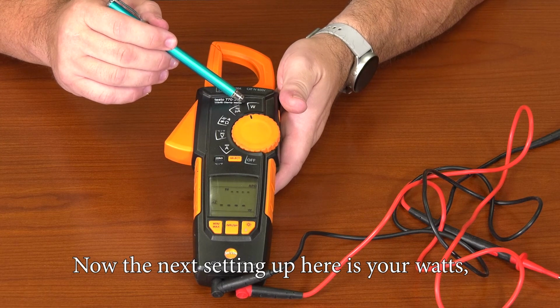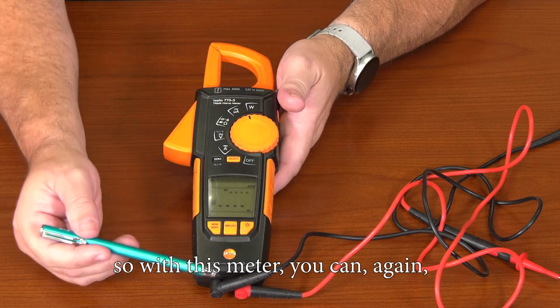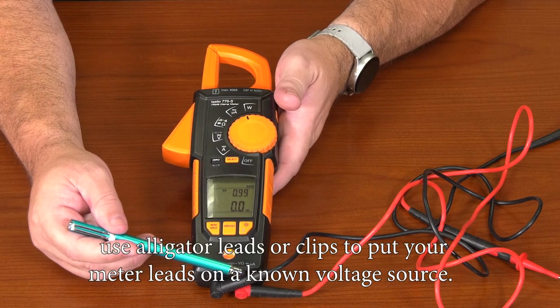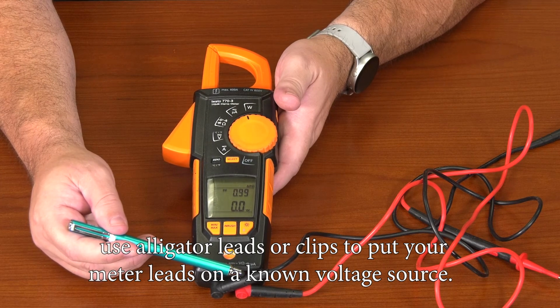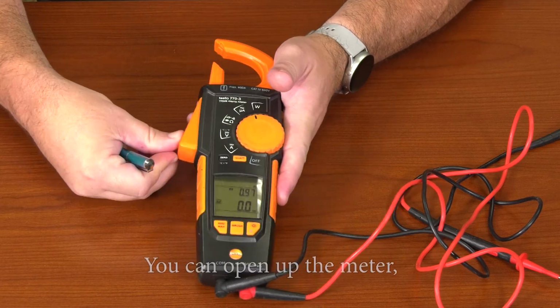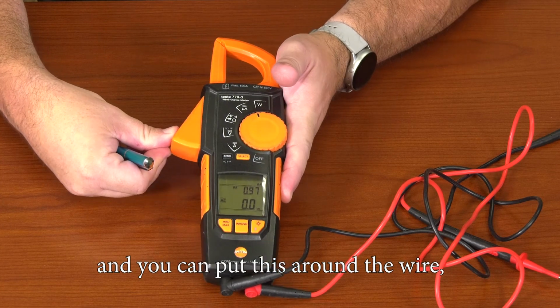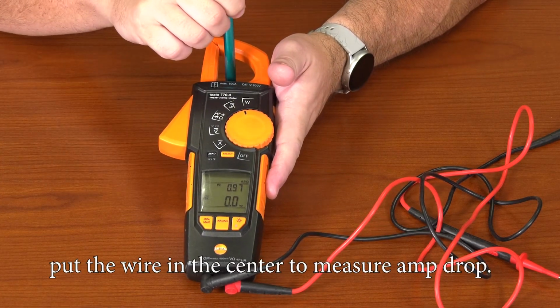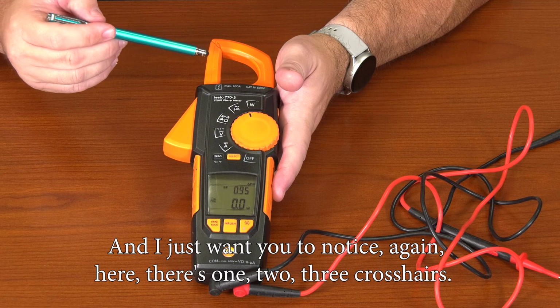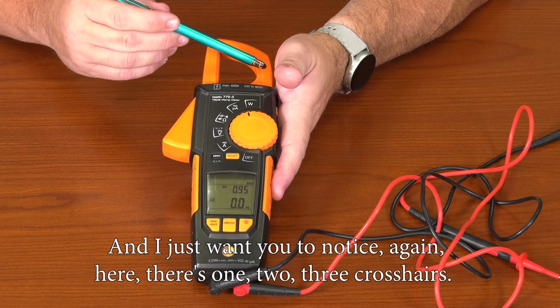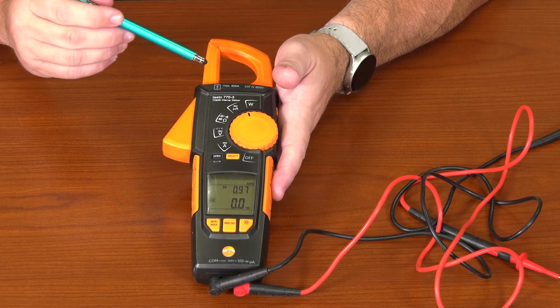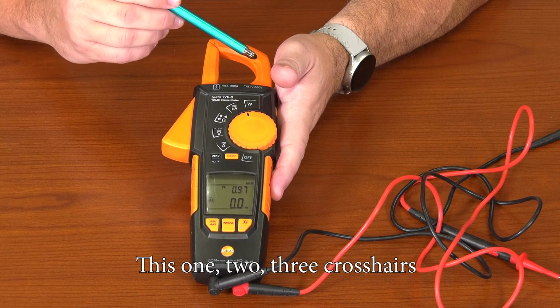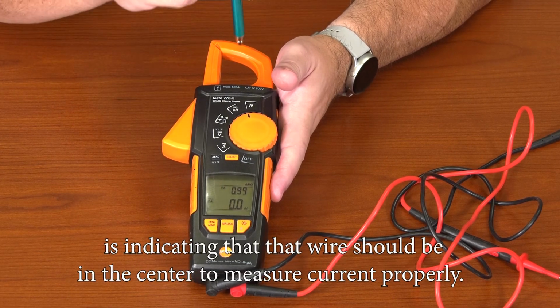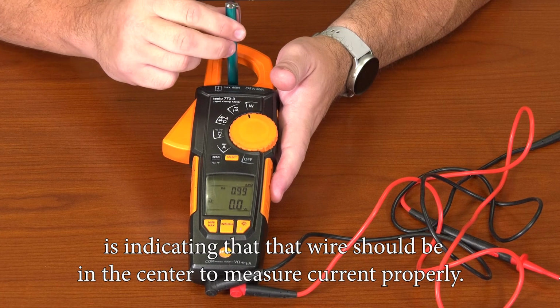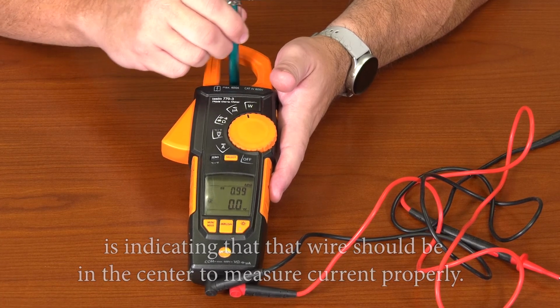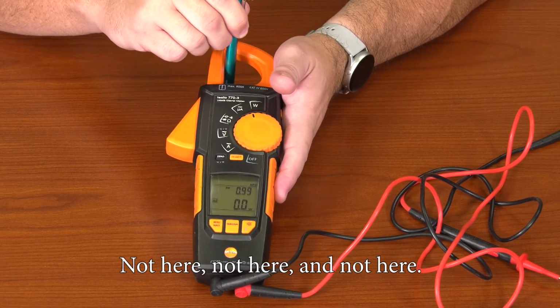Now the next setting up here is your watts. So with this meter, you can again use alligator leads or clips to put your meter leads on a known voltage source. You can open up the meter and you can put this around the wire in the center to measure amp draw. And I just want you to notice again here, there's 1, 2, 3 crosshairs. This 1, 2, 3 crosshairs is indicating that that wire should be in the center to measure current properly. Not here, not here, and not here.